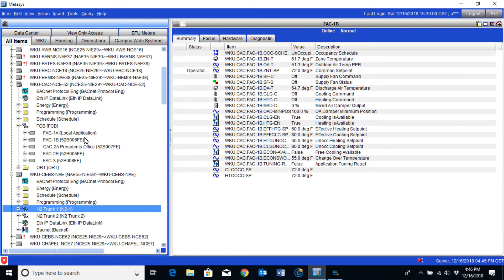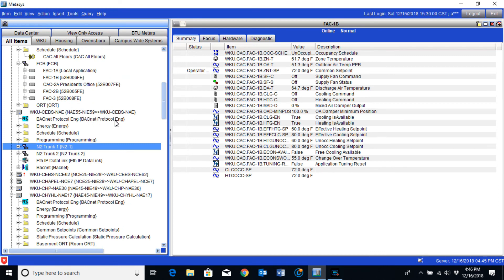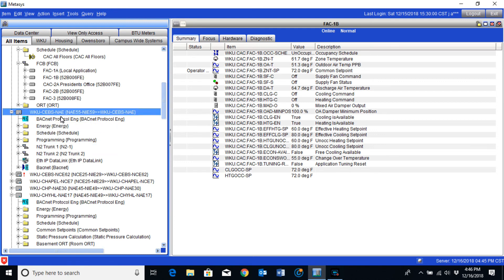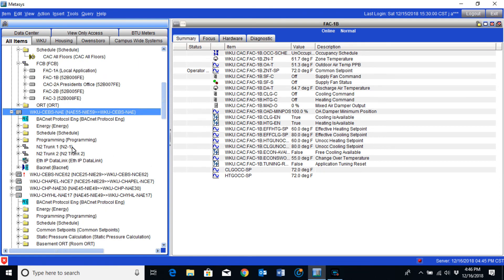Underneath the NAEs, we also see these folders. These folders can have various programming, schedules, and that sort of thing. They are basically a mini-computer and mini-server of their own. Generally, a building should be able to run standalone based off of just the information and the programming that is inside an NAE. Beyond that, if your building is set up correctly, it's a good idea to keep as much programming down to the controller level as possible. That way, if you ever have an issue with an NAE, the controllers themselves can still run.